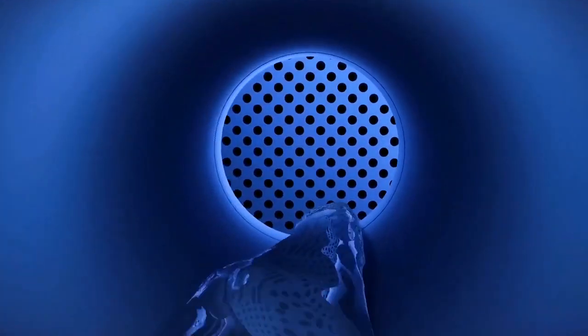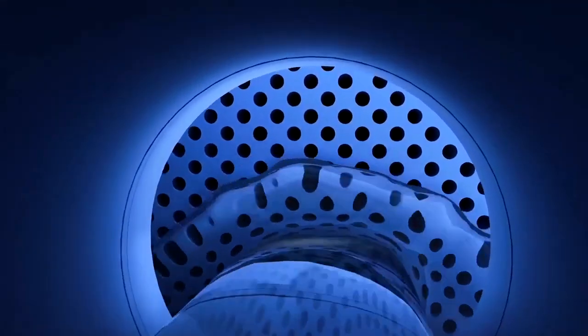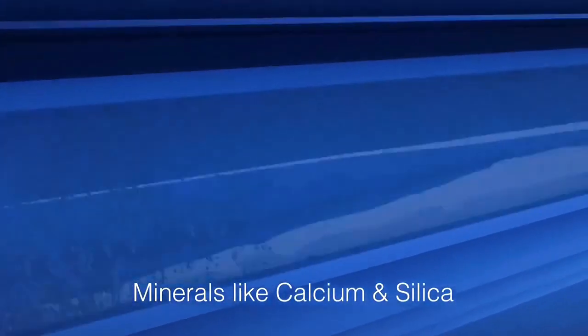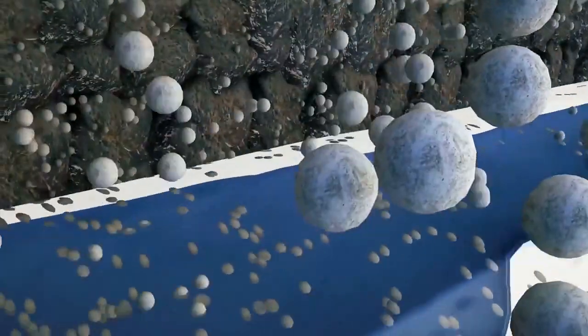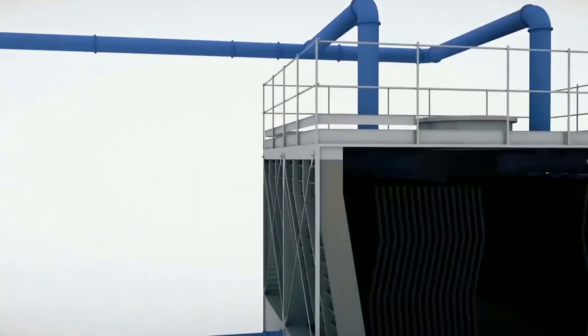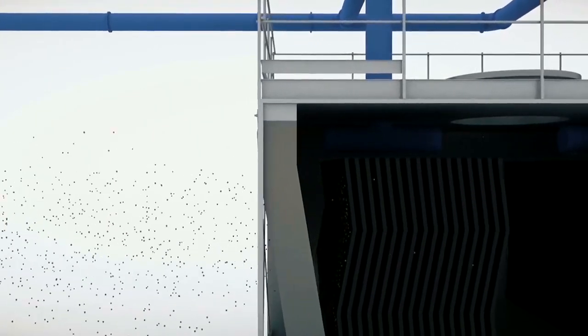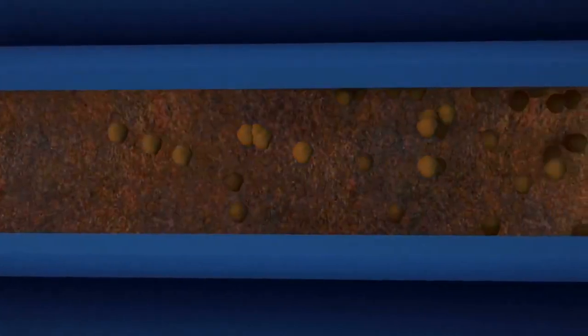Calcium carbonate fouling. Also termed as scaling, it builds up inside the condenser tubes and forms hard scale resembling a plaster/concrete coating that is extremely difficult to remove, either chemically or mechanically. Dust, dirt, and silt fouling. Cooling towers inevitably end up attracting dirt and dust from the surrounding air that settles through the system into the cooling tubes, creating an insulation layer.